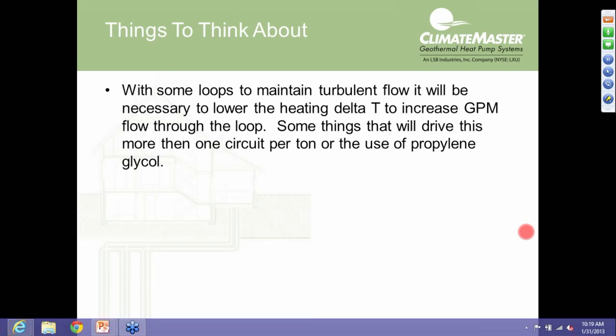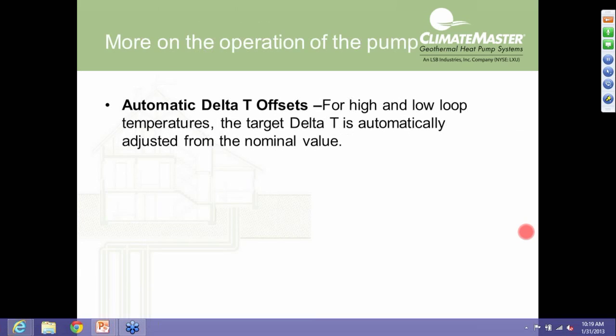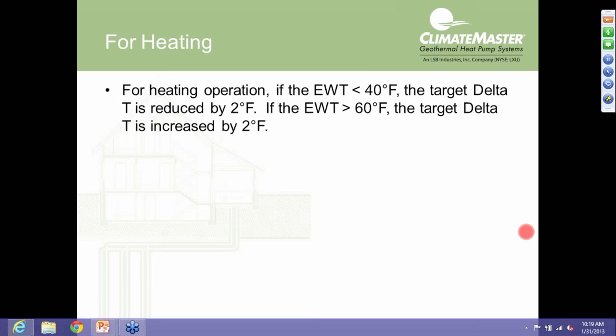Some automatic delta T offsets that are occurring. For instance, in the heating mode, if the entering water temperature, again, is less than 40 degrees, meaning, hey, we're starting to get a cool loop here, we automatically reduce that delta T by 2 degrees. So that factory default of 7 now becomes 5. Again, when you lower the delta T, that speed of that pump goes up. If, on the other hand, the entering water temperature is greater than 60 degrees, we came just out of summer, we're into early fall, we got a fairly warm loop, we increase that delta T by 2 degrees, slowing the pump down, thereby keeping the compressor in a better operating envelope, more efficient.